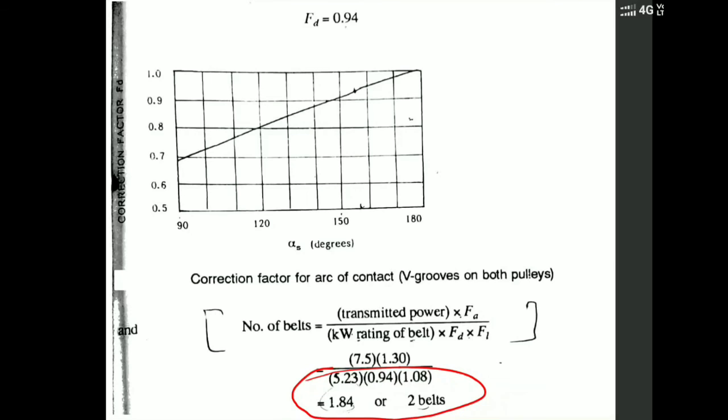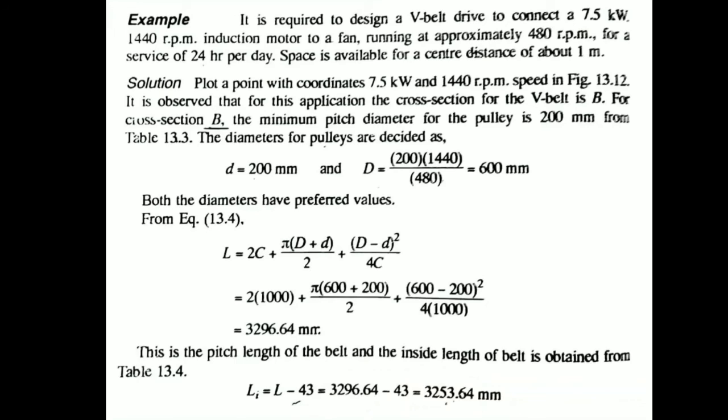Clear? So I hope you understood this process. I have thoroughly explained how we have calculated and designed the V-belt drive. Please check it, understand, solve from your side, and practice. If any query, you can ask me.